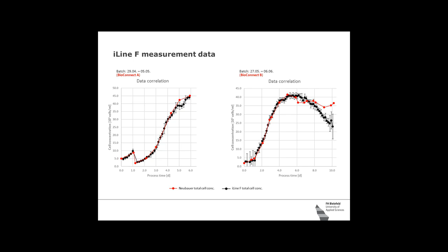It looks like the BioConnect B is not as good in the end of the culture here, days, let's say 8, 9, and 10. But this is due to the fact that we ran the BioConnect, which is a disposable, out of specs here. So the vendor of the BioConnect clearly told us that the BioConnect is good for 3 up to 4 weeks. And this was here the week 11 when we used the BioConnect. So clearly out of specs. Why we have the deviation here in cell concentration is not really clear, but if you drive something out of the specification, there should be a reason why there's a certain limit to use this.